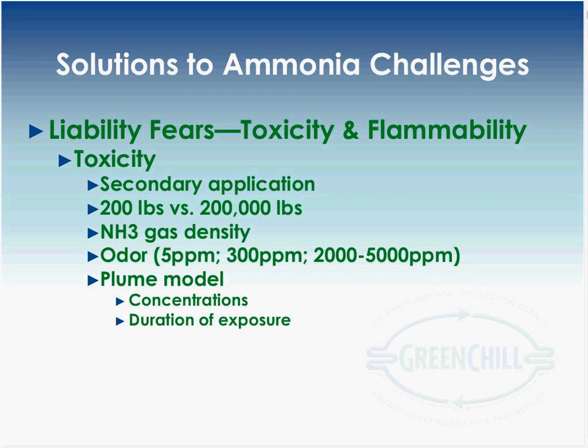On ammonia gas density, it is lighter than air. So if ammonia gas is leaked, it will rise and get diffused into the air versus concentrating as it pools. And then the other item there is the odor, and I put parts per million there just to highlight some key levels. There's a low level at which you can detect ammonia with your smell, and then 300 parts per million is about the point at which you're not going to be hanging around; you're going to be getting out of the area. So you've got those two warning steps, and then beyond that, it's 2,000 to 5,000 parts per million with exposure of more than 30 minutes before you can start to have trouble.